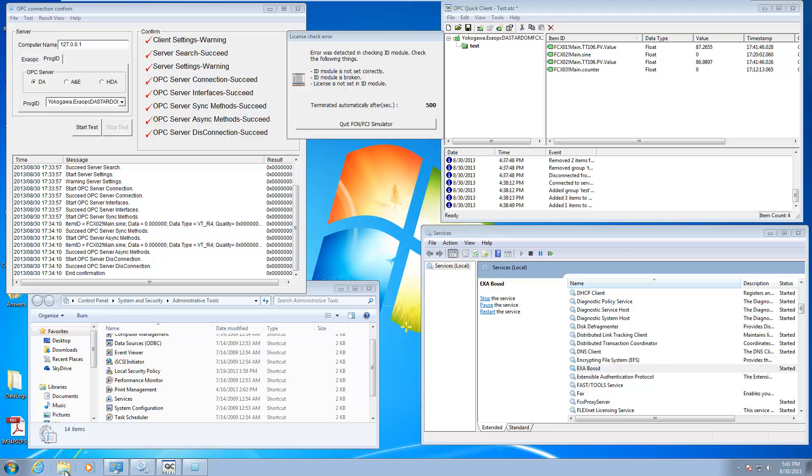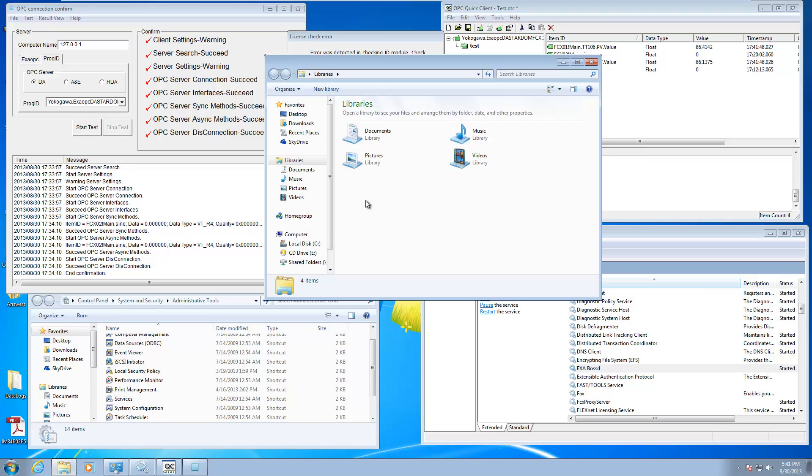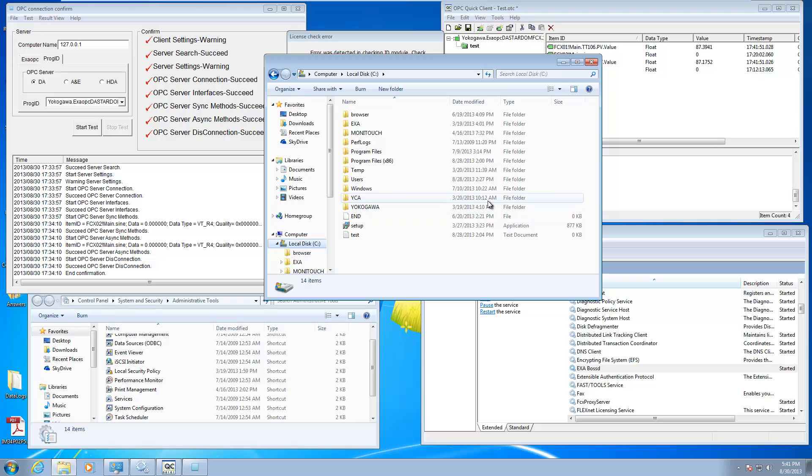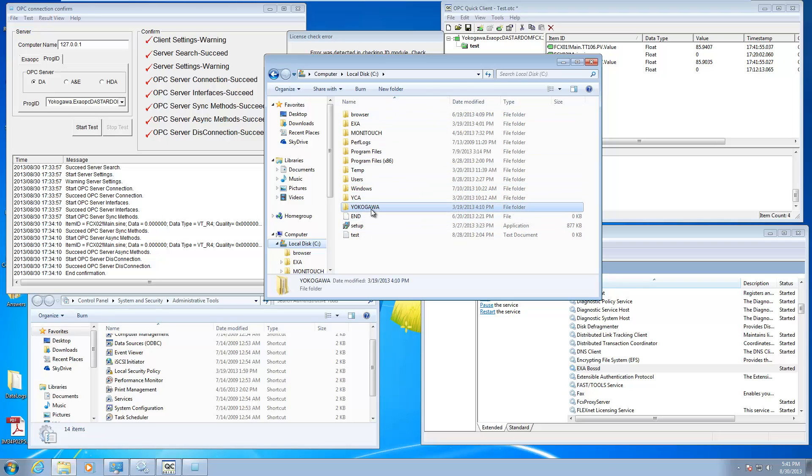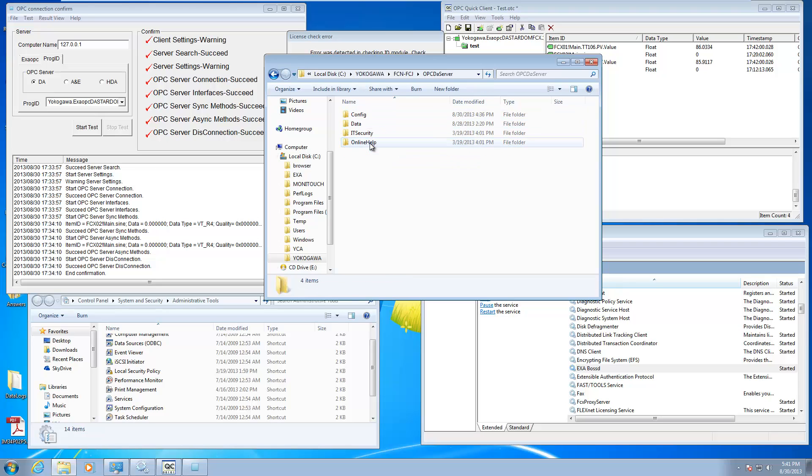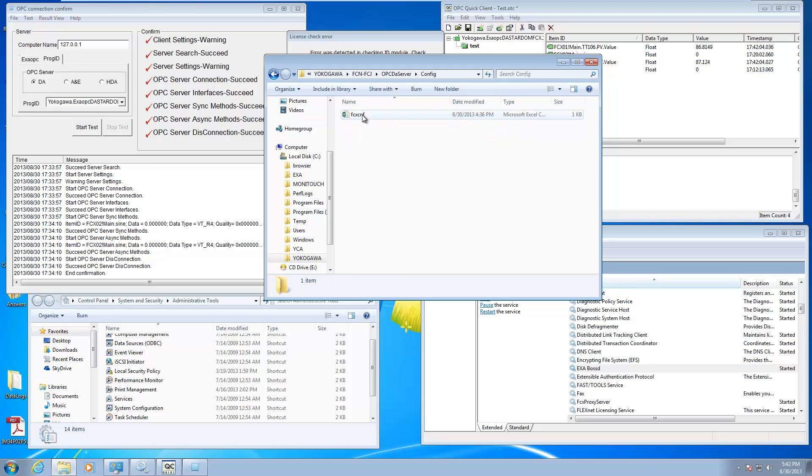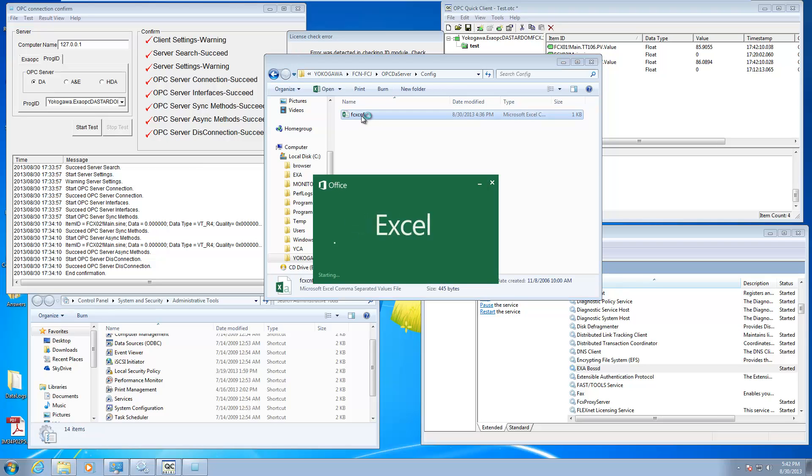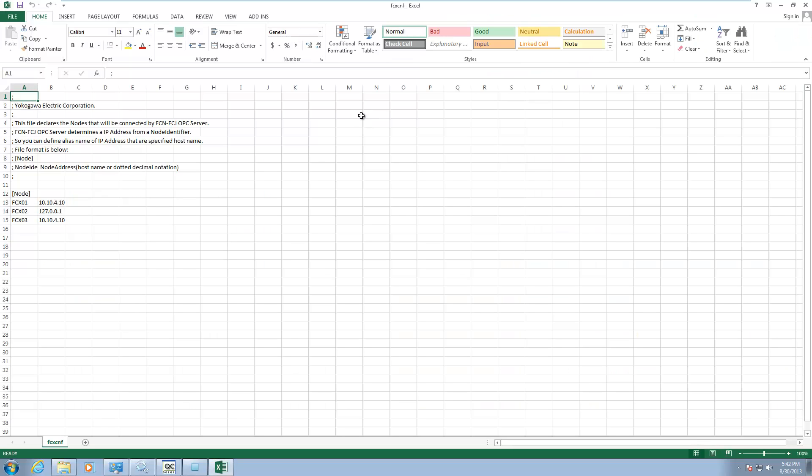What the manual is going to tell you to do is you're going to browse to where the OPC server is installed. By default, it goes to the Yokogawa directory on the C drive under FCN FCJ OPC DA server. There's going to be a folder here called config. In that folder, there's going to be a comma separated file called FCX CNF. This is pretty much the key to getting this all to work.